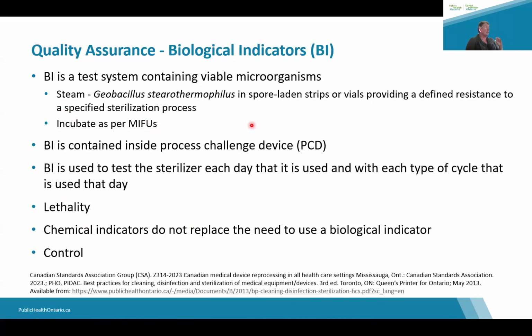For steam, the organism that is being used is Geobacillus stearothermophilus, and it usually comes in either strips or vials, and you incubate these per their MIFU. So you can see that MIFUs are really important. BIs are placed inside a process challenge device, and we're going to talk about those in a couple minutes. And the BI, again, is used to test the sterilizer each day that it's used with each type of cycle that it's used. So if you run different types of cycles, then you need to run a BI on each of those cycles. Chemical indicators do not replace the need for a biological indicator because they cannot demonstrate lethality. And when you run a BI and incubate it, you also have to have a control. And this is to make sure that the BI is actually viable.